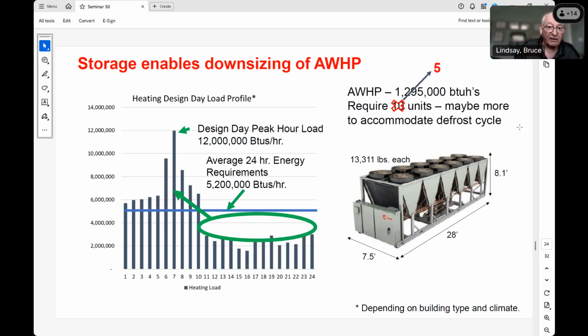I'm not going to go much detail other than say that this is a trick. If I have to size my system for my peak hourly load, I need to put in 10 of these monster heat pumps on the roof. But if I can go with thermal storage, I can size for the average, and all I need is 5 of these units. So this is critical for the success of these systems. Yes, you have to add tanks with these systems. You have to find the space for them, but there's always a lot more space in a building for tanks. There's no more space on the roof. Next slide.